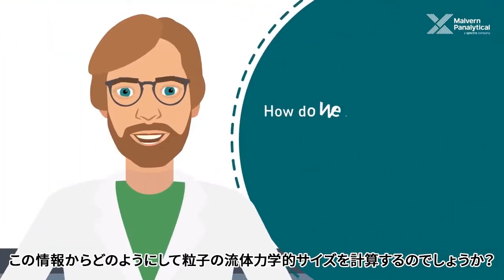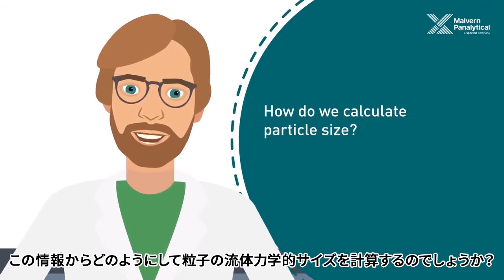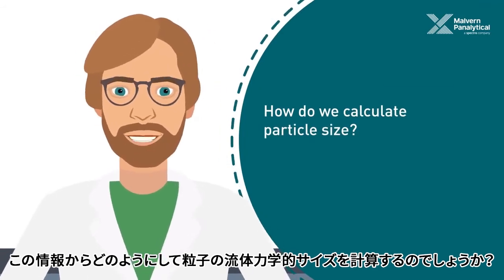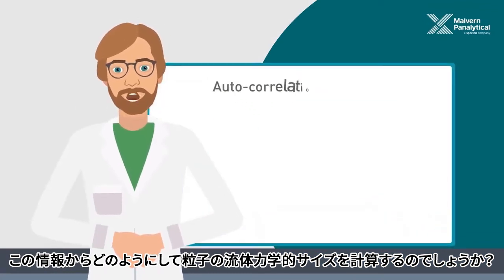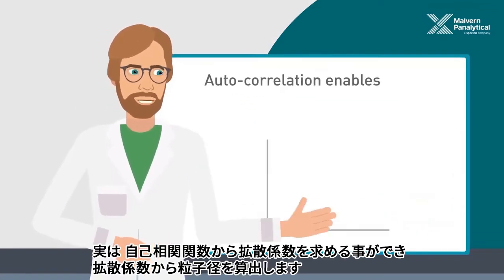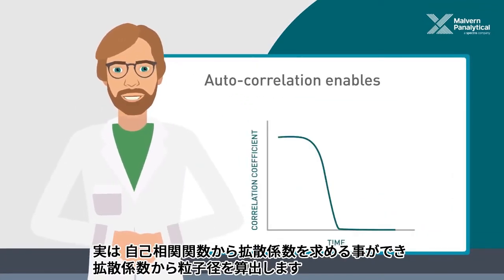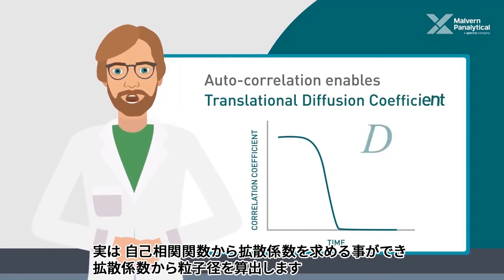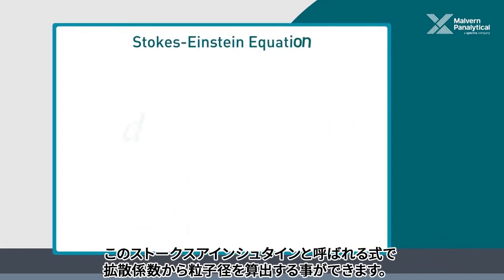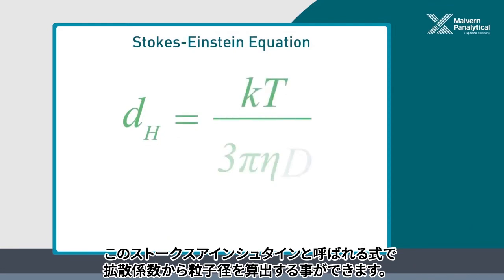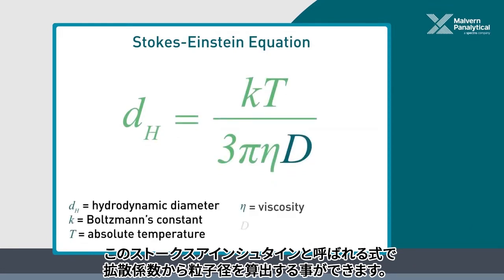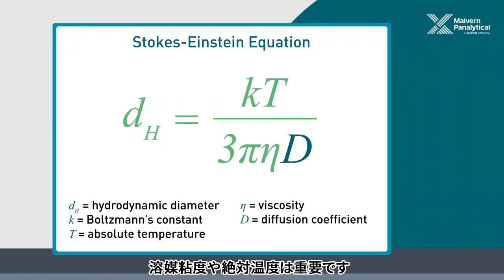So how do we use this information to calculate the particle's hydrodynamic size? The autocorrelation function we've created enables us to extract the translational diffusion coefficients mentioned earlier. These values are used in the Stokes-Einstein equation to obtain our size information. Variables such as solvent viscosity and temperature need to be known, because they'll affect the particle's diffusion rate.